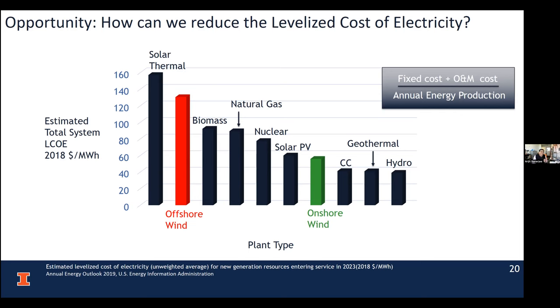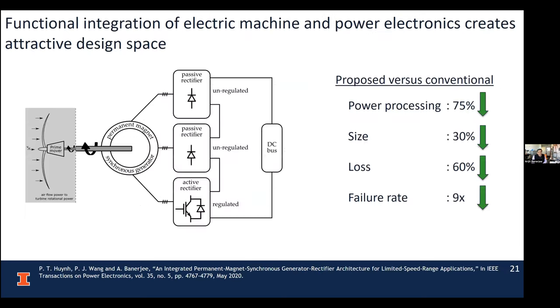The architecture we'll be talking about today follows our fundamental approach of looking at the machine, power electronics, and control together — what we call the integrated generator-rectifier architecture. You'll see that with this architecture, we can reduce power processing by 75% compared to a conventional system, reduce size by 30%, reduce loss by 60%, and — most interesting to me — reduce the failure rate by 9x.